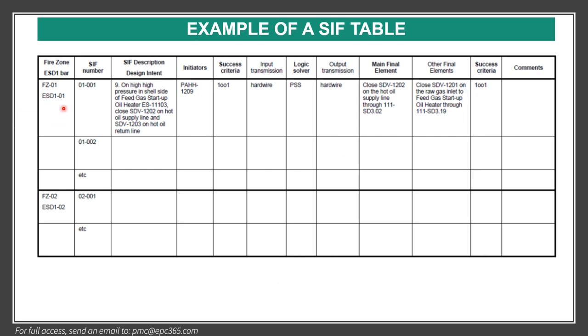This is an example of a SIF table that must be ready before the workshop. It has to be agreed with the company, contractor, and the chairman of the SIL. We write here, for example, fire zone one, ESD level one. This includes the SIF number, SIF description, what the initiators are — for example, pressure alarm high-high — the success criteria such as one out of one, the transmission hardware, the logic solver as part of ICSS, output hardware, and the final element, which is an SDV.